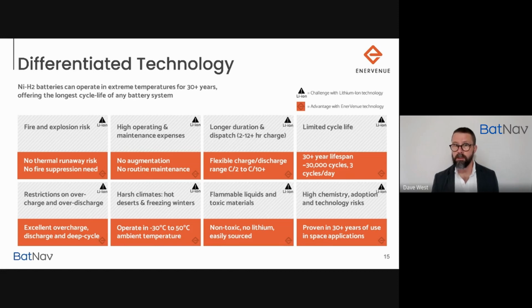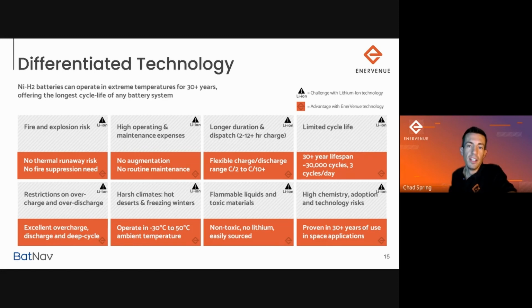Right, and then also looking at our life cycle - over 30 years, 30,000 cycles, which equates to operating at 3 cycles per day for 30 years. That means back-to-back cycling, no need for any resting period. You can really put the pedal to the metal, operate it hard, and it's for all intents and purposes an unlimited life cycle battery. You're never going to get to 30,000 cycles. And again, all without augmentation.